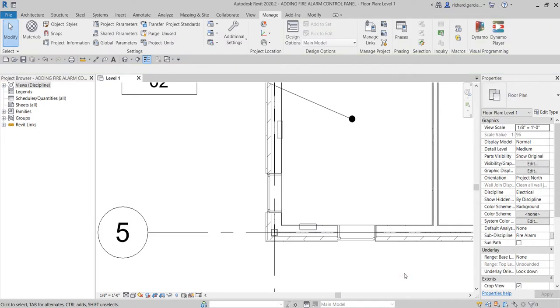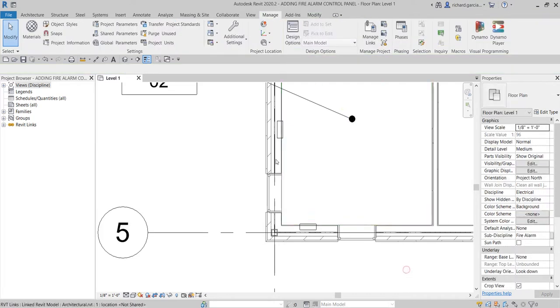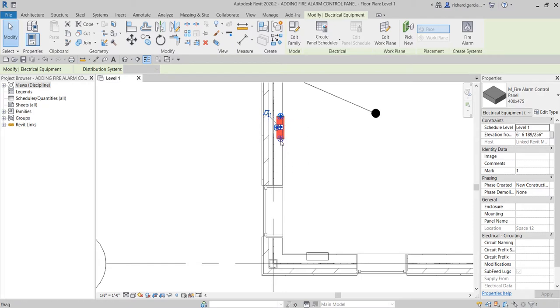You can use metric or imperial units — just make sure you type the unit symbol. I'll select the second panel and change it to 2000 mm and click outside to apply. This is very important: if you're creating a family for the panel, make sure you put connectors in it. As you can see, I have four connectors — I can generate conduit from them and I can also create a fire alarm system from here.